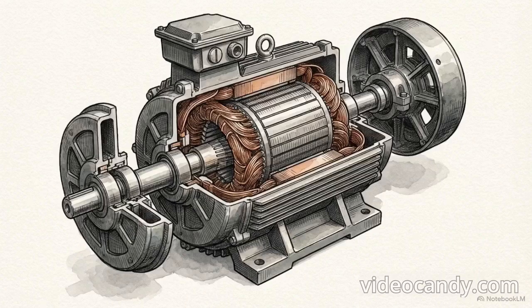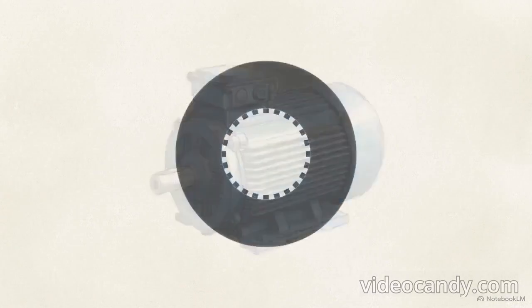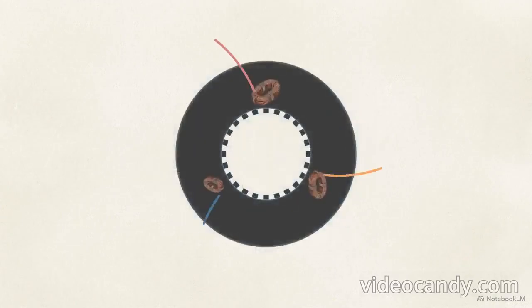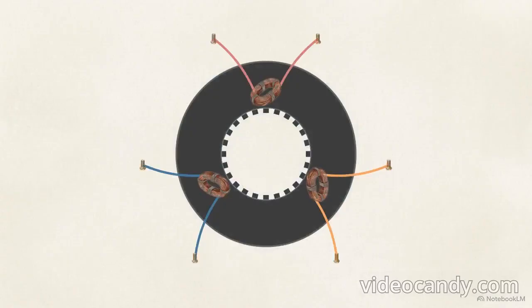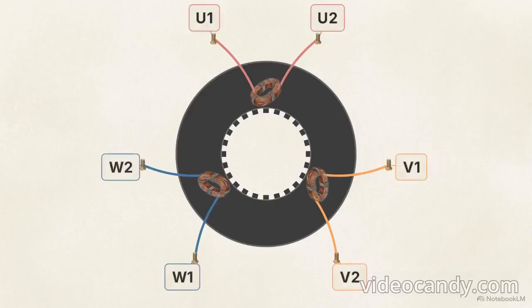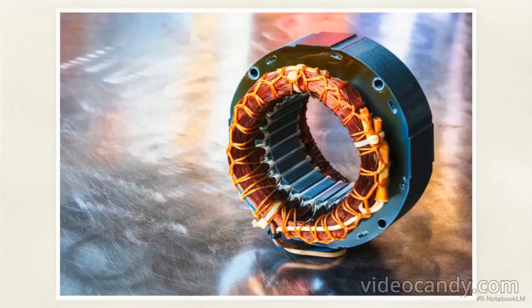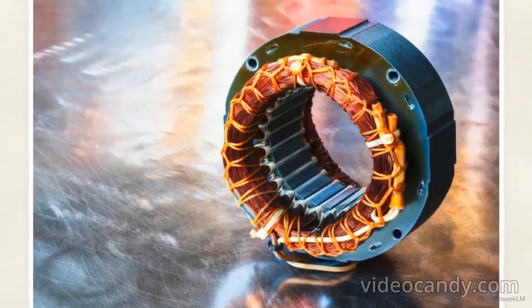To bypass the limits of direct online starting, we must look past the heavy cast iron housing and examine the raw magnetic topography inside the motor itself. A standard 3-phase stator is constructed from 3 isolated electromagnetic coils wrapped around a laminated steel core. With 3 individual coils, there are exactly 6 distinct wire ends to account for. These are designated as U1 and U2, V1 and V2, and W1 and W2.